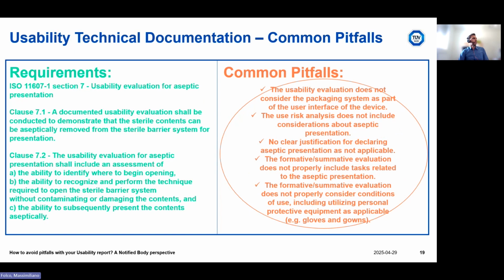Last slide is related to a different standard, ISO 11607-1 for non-active medical devices. So usability evaluation for aseptic presentation is required in section 7 of this standard, related to the sterile barrier system of non-active medical devices. Aseptic presentation is defined as the transfer of sterile contents from its sterile barrier system using conditions and procedures that minimize the risk of microbial contamination. So transferring a sterile device from the sterile packaging, so from the sterile barrier system, minimizing the risk of its microbial contamination. The sterile barrier system is defined as the minimum package that minimizes the risk of ingress of microorganisms and allows aseptic presentation of the sterile contents at the point of use.